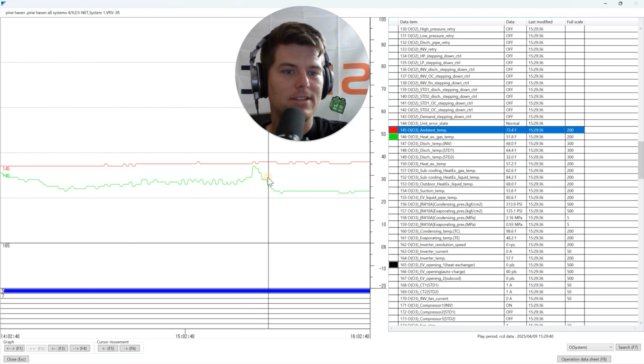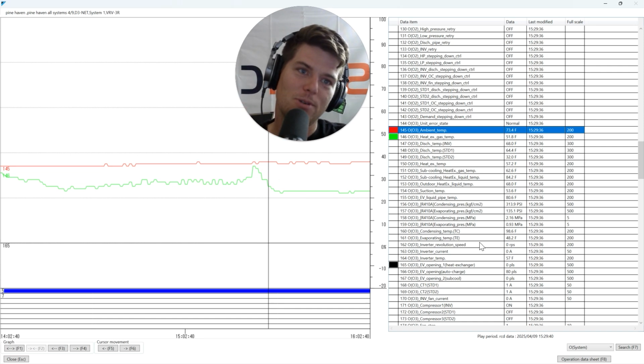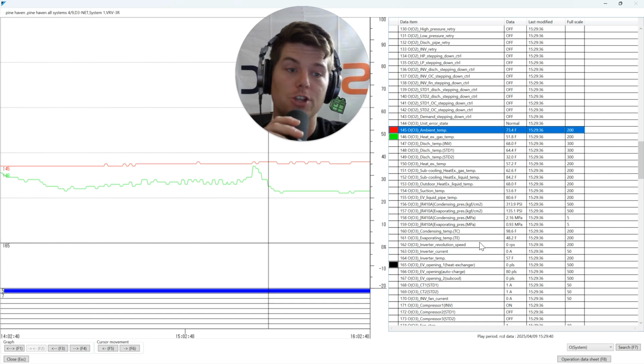Well, why would this come back down if the pulses are still at 0? Because it's bleeding liquid refrigerant by. Oh, no, there it is. That's where it's coming from. So sub 2 module is letting liquid refrigerant go through the outdoor heat exchanger on this particular module at 1 step, and it's flooding back. Now, how else can we measure this?